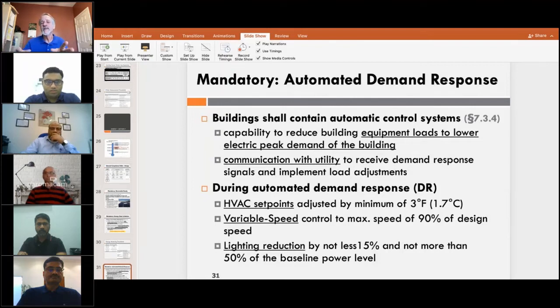There are ways of looking at it. Buildings can sense that, maybe get a signal from the utility that says, please reduce your load by 5 or 10% or whatever they were asking for. So what we're saying here in the standards is the buildings should have that capability to automatically control the equipment loads to lower the peak demand. And some of the suggestions are things like HVAC set points.